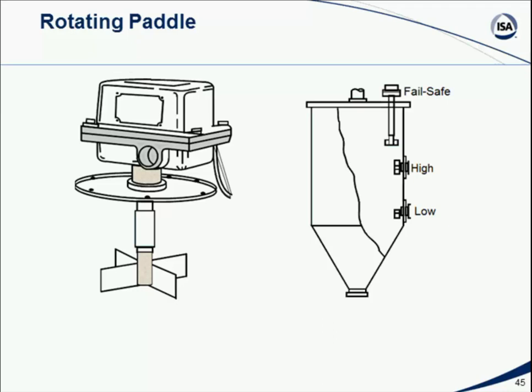So in the example we're showing here, we've got a bin where we've got a paddle at the bottom of the bin, at our low point, we've got a paddle at the high point, and we've got a fail-safe paddle sticking in from the top. So what does that mean? It means that I can determine if the material level in the bin drops below the low level, because then the paddle there is uncovered. I can tell if the material in the tank is above the high level. Why? Because the high level thing isn't turning. And I can tell if we've gone too high up in the tank because the fail-safe paddle stops turning. So I don't have an exact level measurement. All I've got is an indication that I'm at the bottom or top or way too high in the tank. So sometimes point measurements are perfectly adequate.